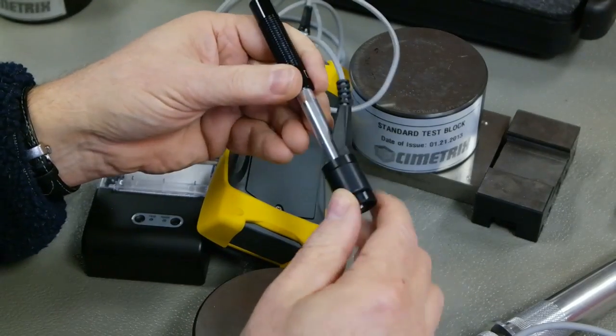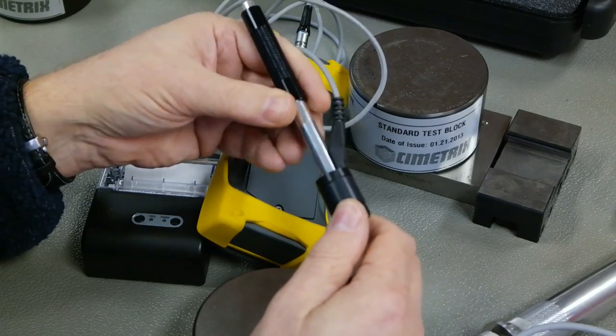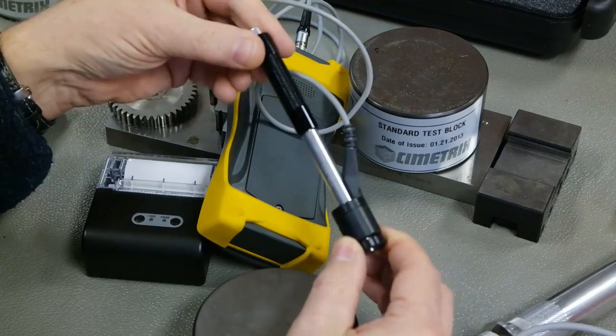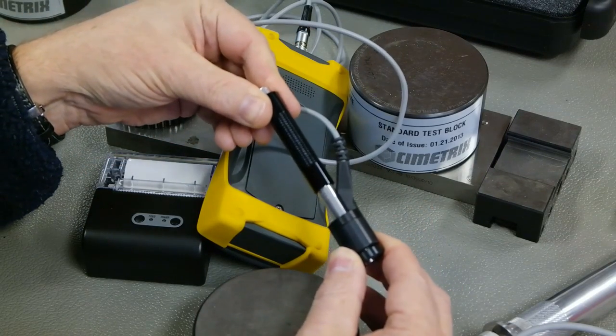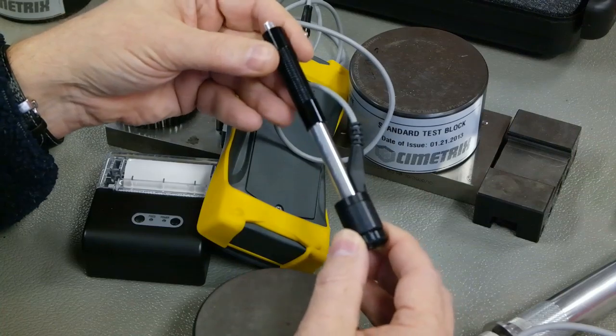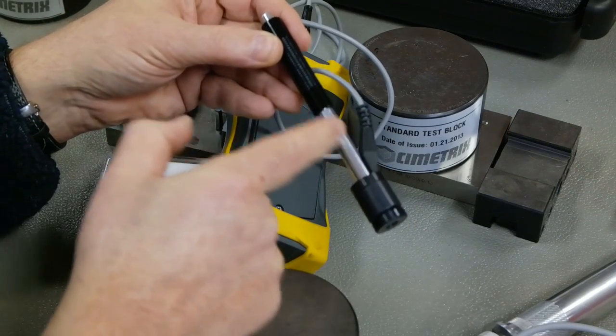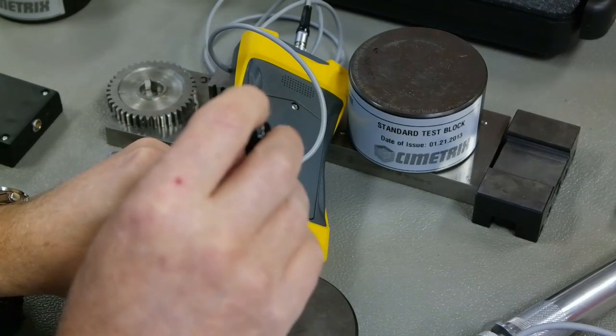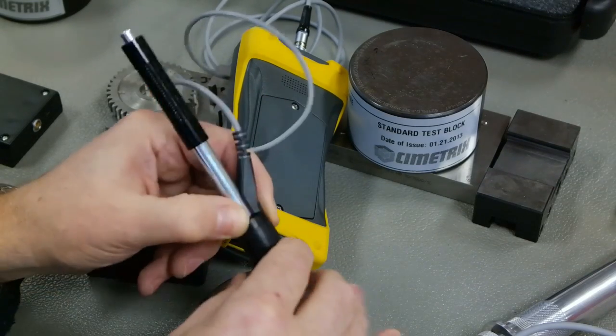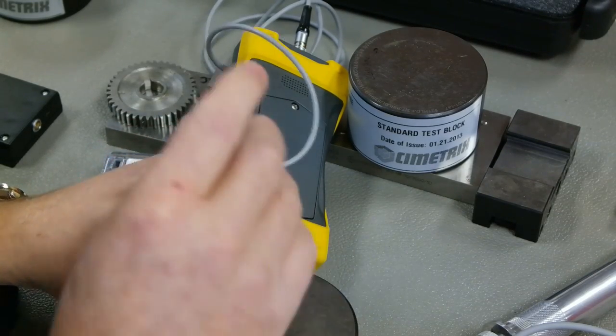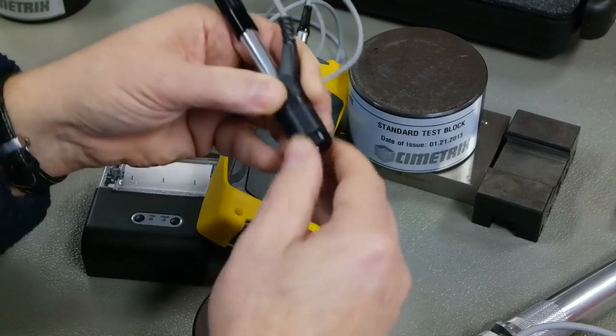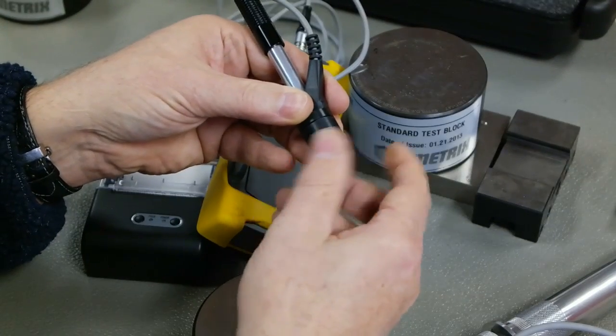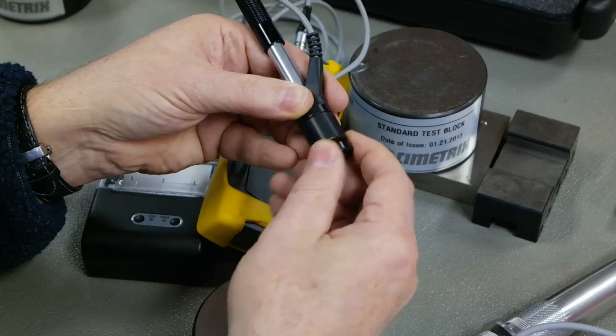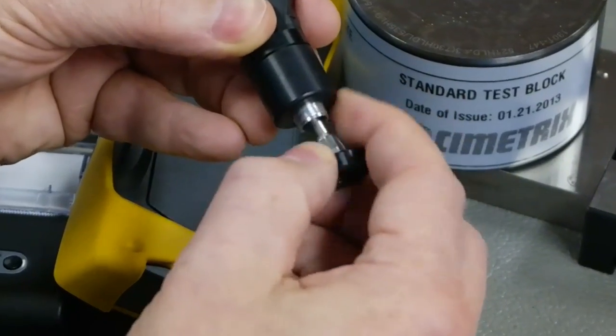So this is what we call a Leeb type probe. What we do is push down on the handle, and a little click happens, and what it's done is grabbed a thing called the impact body and pulled it up inside. So when we do a test against a part, we press the little button on top and it fires this impact body at the material. So if I just do a quick test here, I'm going to screw off what we call the support ring, and this allows you to take out the impact body, and this is the little guy here.